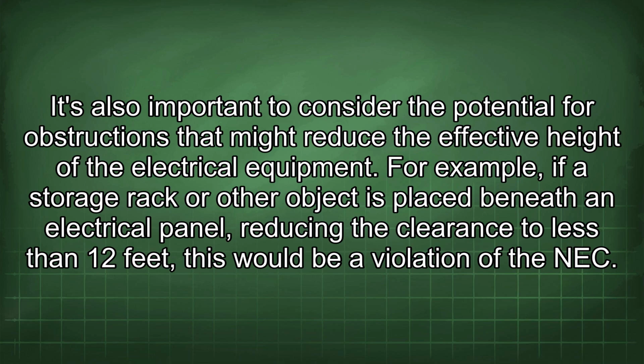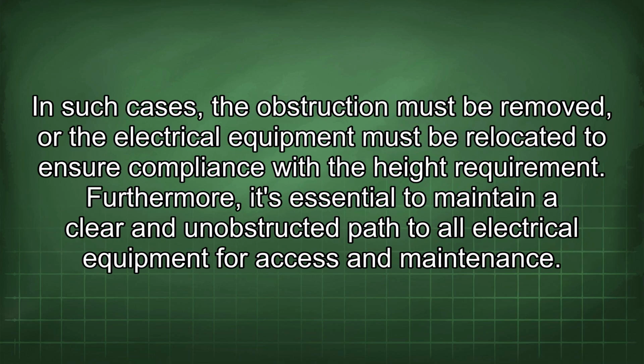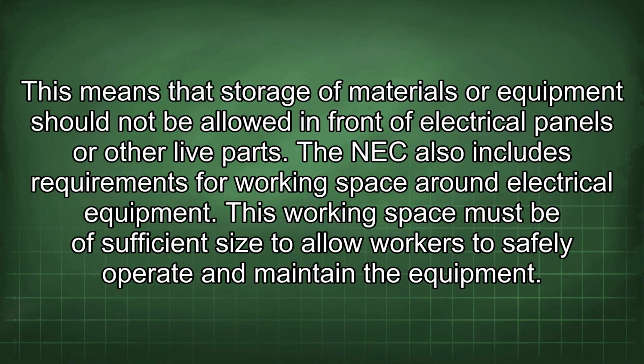This may require the use of pendant-mounted fixtures or other specialized installation methods. It's also important to consider the potential for obstructions that might reduce the effective height of the electrical equipment. For example, if a storage rack or other object is placed beneath an electrical panel, reducing the clearance to less than 12 feet, this would be a violation of the NEC. In such cases, the obstruction must be removed, or the electrical equipment must be relocated to ensure compliance with the height requirement. Furthermore, it's essential to maintain a clear and unobstructed path to all electrical equipment for access and maintenance.